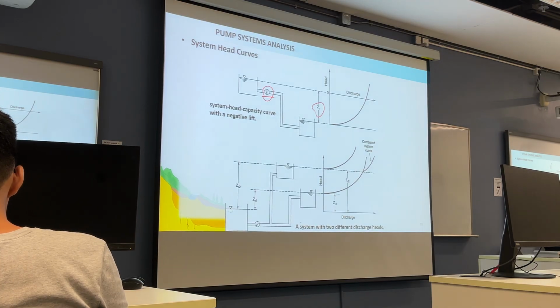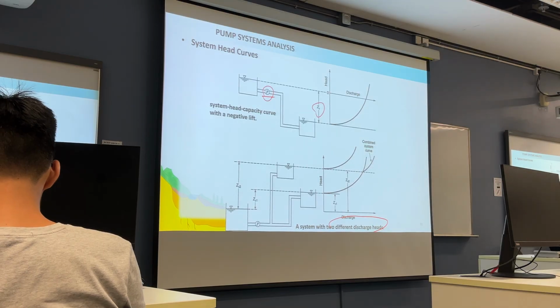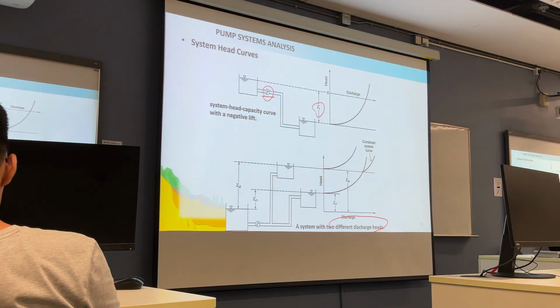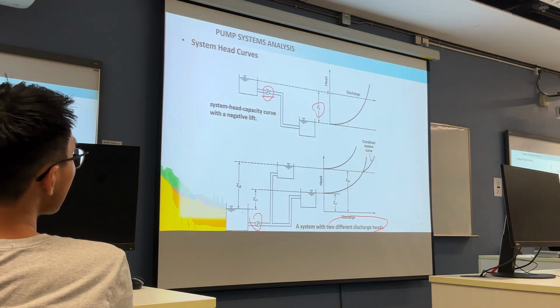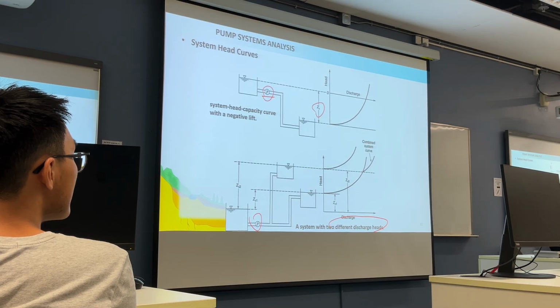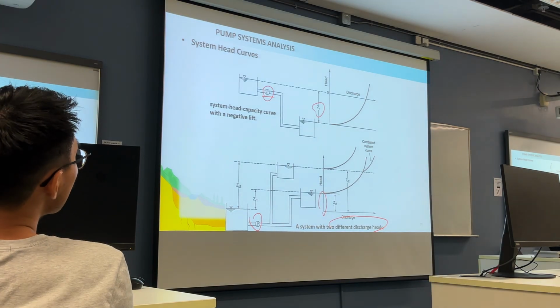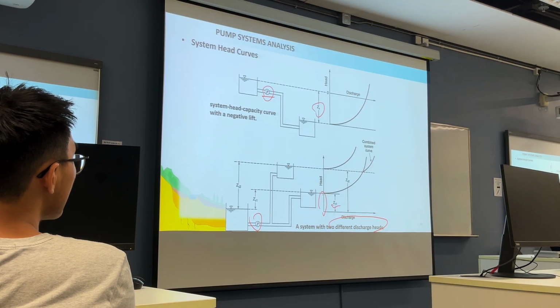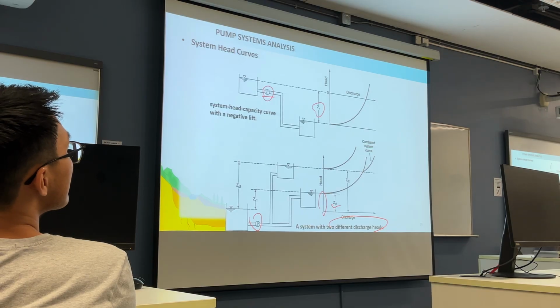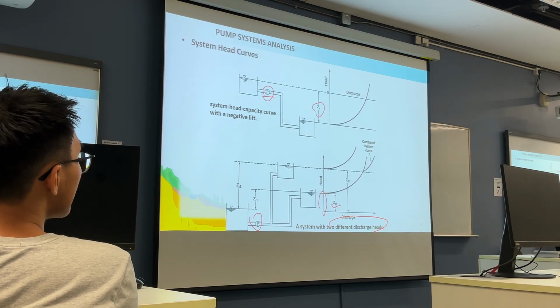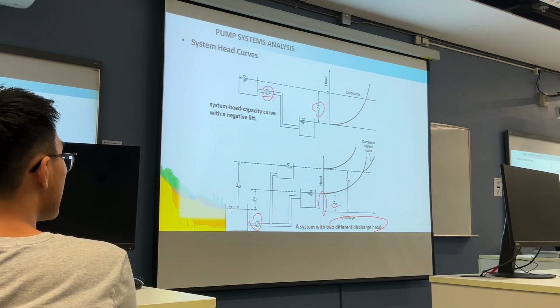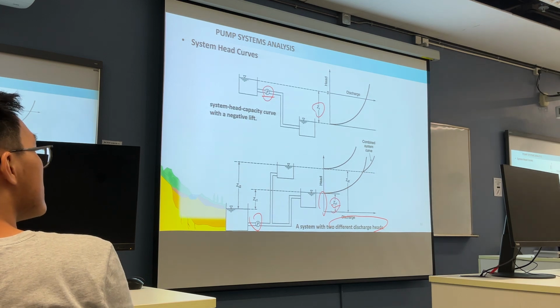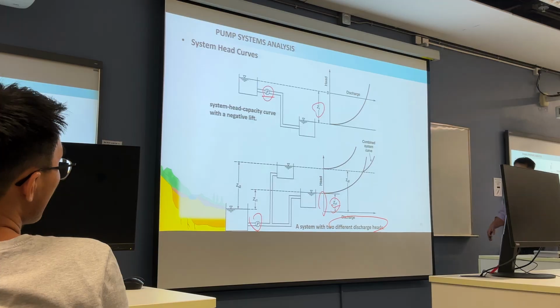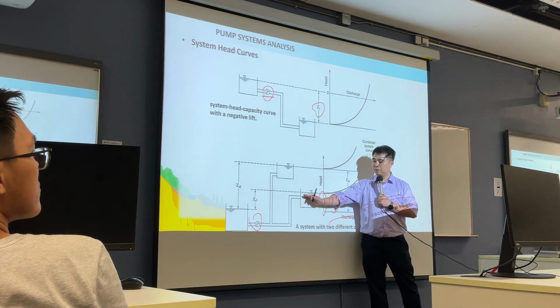Now the bottom one is a system with two different discharge heads, with two receiving reservoirs, okay? That means if you use one pump to provide the head to pump the water, and the head just reaches this level, ZS1, it only reaches ZS1. Because you can adjust the rotational speed of the pump to control the pump's working status, if you just want to pump water to this reservoir, you only need to make the pump work at a head near this head, okay? So you can control it so the pump only pumps to this reservoir.